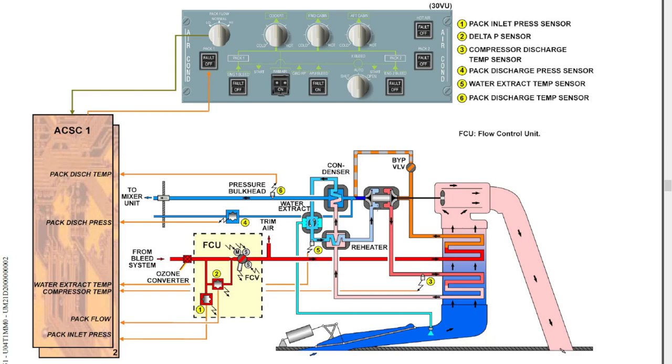Here the temperature goes to a very low value, because now you had air at a certain high temperature coming to the turbine, and that heat energy which was in the air was used to turn the turbine. Energy conversion: that air will lose its heat energy, and that heat energy gets converted to kinetic energy, and that kinetic energy turns the turbine. Air will lose its heat, and you will have sub-zero temperature air which will come out from the turbine.